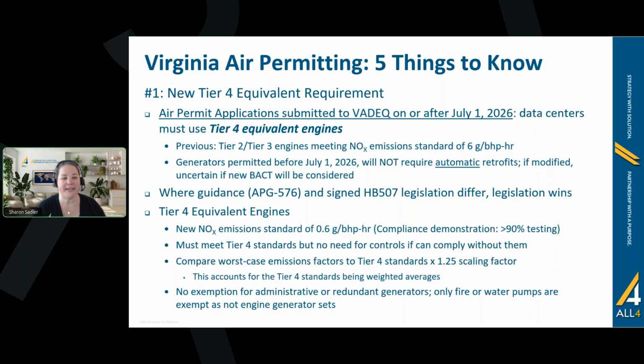First up is probably the biggest news for Virginia data center air permitting, and that's the new legislation and guidance around Tier 4 equivalent generators, even for emergency purposes. If you haven't heard of this requirement, here's what it says: for air permit applications submitted on or after July 1st, 2026, data centers need to put forward Tier 4 equivalent engines. For most engines, this will require a selective catalytic reduction (SCR) unit for NOx reduction, potentially a diesel particulate filter for PM control, and potentially an oxidation catalyst for carbon monoxide control.